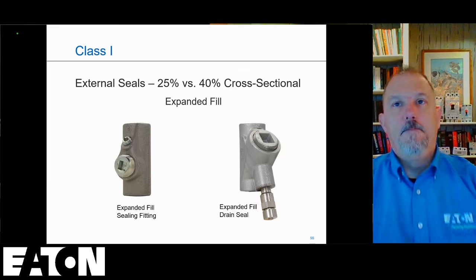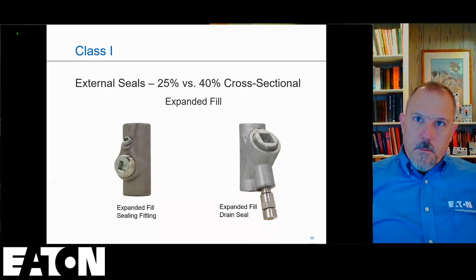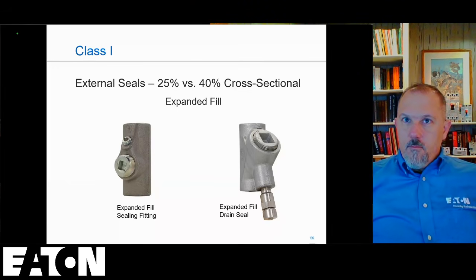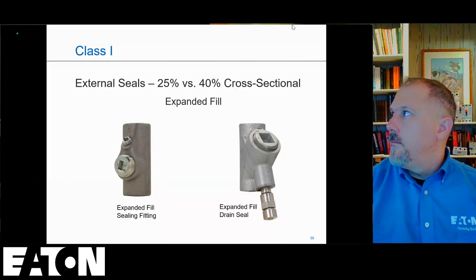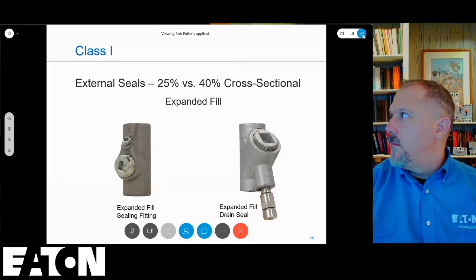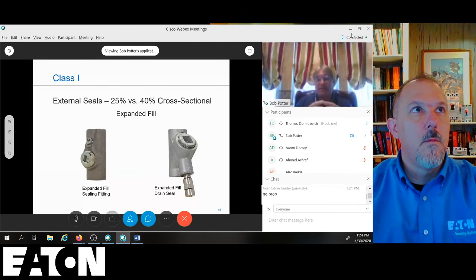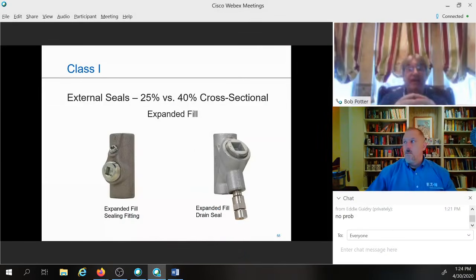If it's open cabling, you're going to have a cable gland, and that cable gland is going to act as the sealing fitting. The sealant in that case will be in between all the conductors and not allow the gas to travel through that cable core, for cables that can transmit gas and vapors through the cable core.